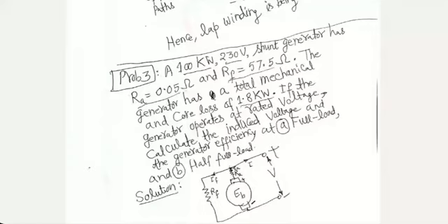Here they say 100 kilowatt. This number, by the way, the 100 kilowatt number and the 230 volt number, will be mentioned on the nameplate of the generator. This generator is capable of delivering 100 kilowatt. This is the DC case, so power factor is 1. Don't worry about imaginary power here. It's all real power. 100 kilowatt power is the rated output. 230 volt is the rated voltage.